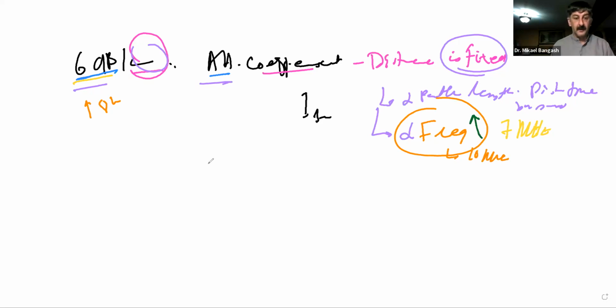Although we had the formula to calculate it with the help of frequency: the attenuation coefficient is equal to the frequency divided by 2. So practically, with a 7 megahertz transducer, it should have been 3.5. Clear? With a 10 megahertz frequency, it would have been 5 decibels per centimeter, actually. But you can say that the greater the frequency, the greater the attenuation coefficient, where the distance for your attenuation coefficient is fixed at 1 centimeter. Did that make sense?